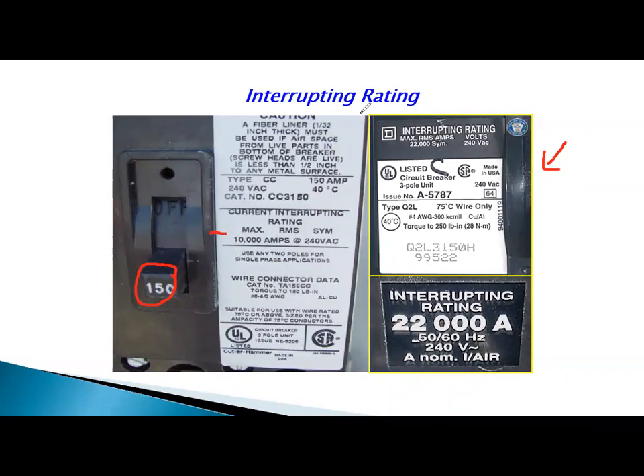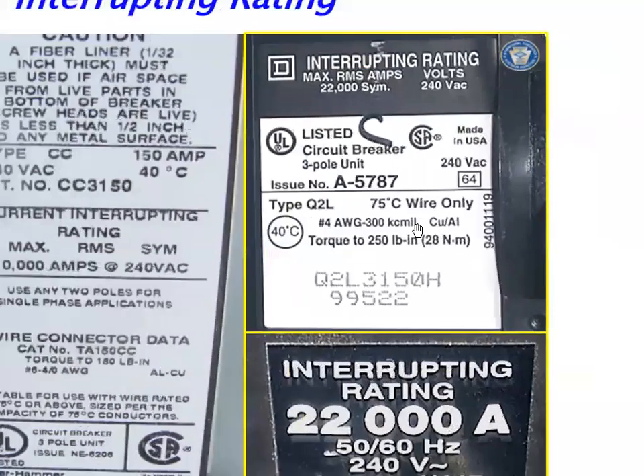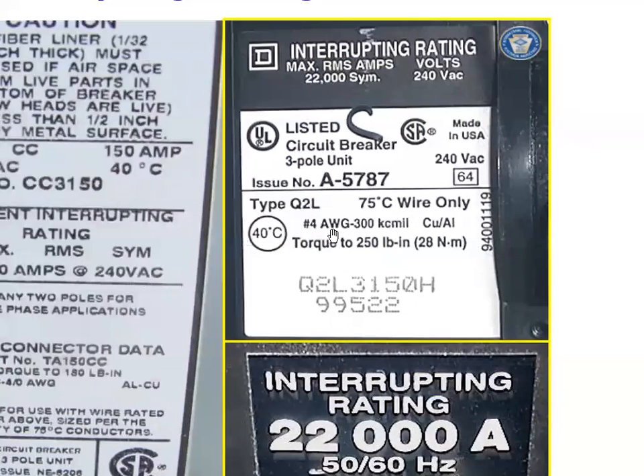I cut these two breakers in half. One is over here, the other is over here. On this one over here, we can see 22,000 amps. A lot of other information on these breakers, just so we get a good idea, right? So if I increase this just a little bit and zoom in, we can see that this breaker on this right-hand side is for 240 volts AC. That is it, nothing else.